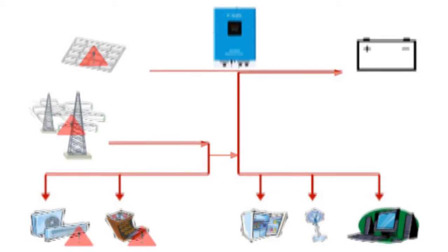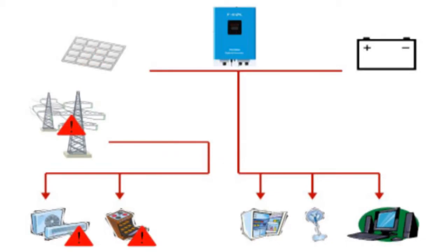If the grid goes down, the inverter will continue to energizing your off-grid loads. However, the inverter will stop energizing your on-grid loads while the grid is down for safety and legal reasons. This feature is called anti-islanding.